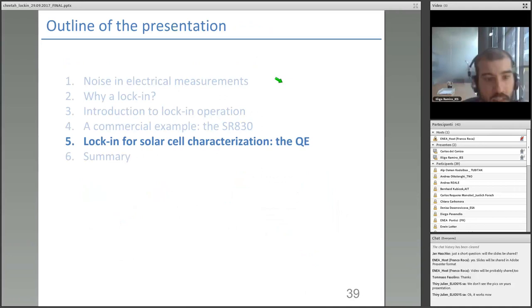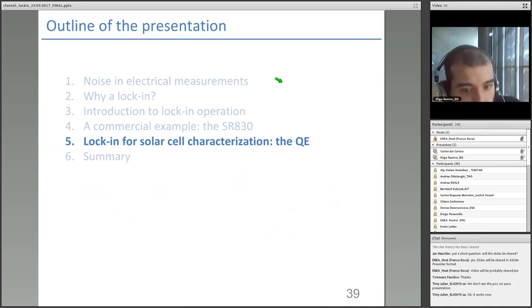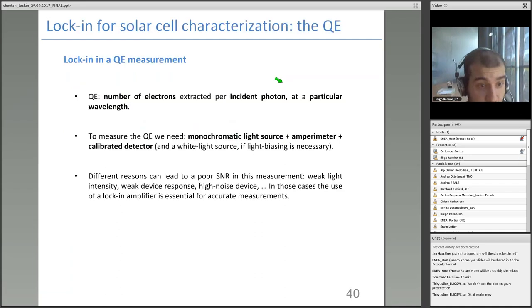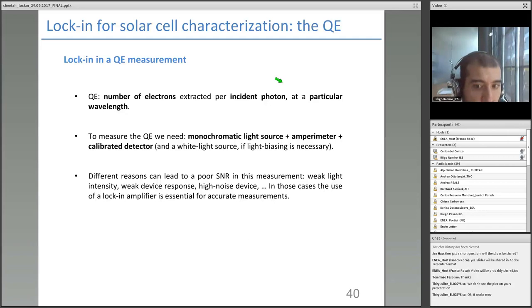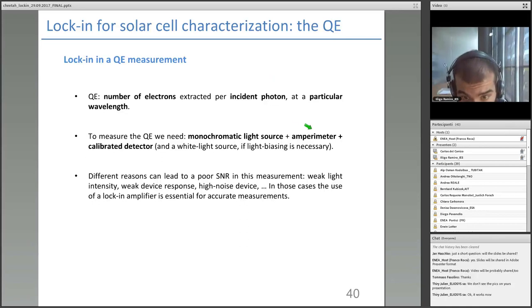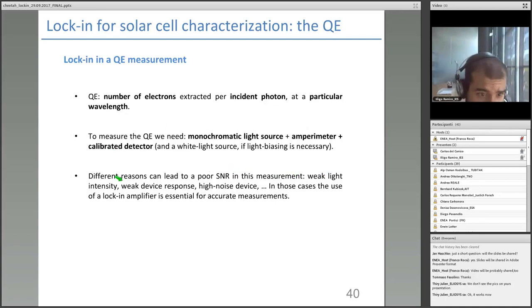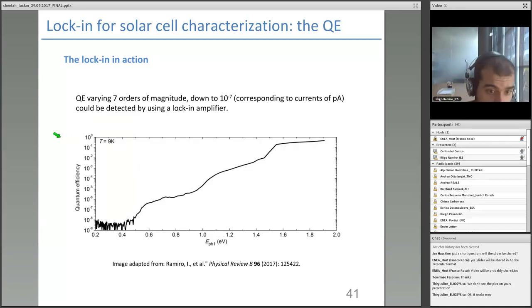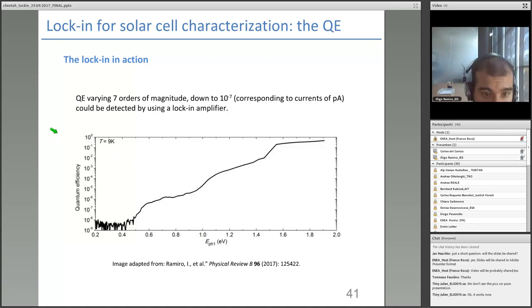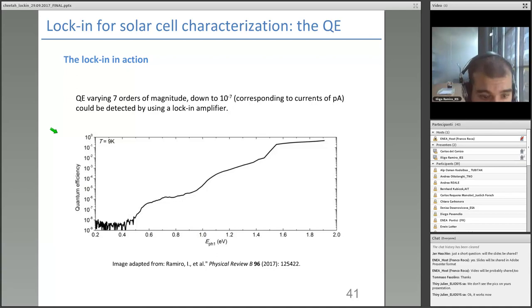Let's move to the use of lock-in for solar cell characterization — the example of quantum efficiency. Quantum efficiency is the number of electrons generated per incident photon, and to measure it we need a monochromatic light source, an ammeter, and a calibrated detector. The lock-in acts as the ammeter for noisy measurements caused by weak light intensity, weak device response, or a noisy device. As an example, here is a quantum efficiency measurement varying over more than seven orders of magnitude, measured using a lock-in amplifier — showing how powerful this technique is.